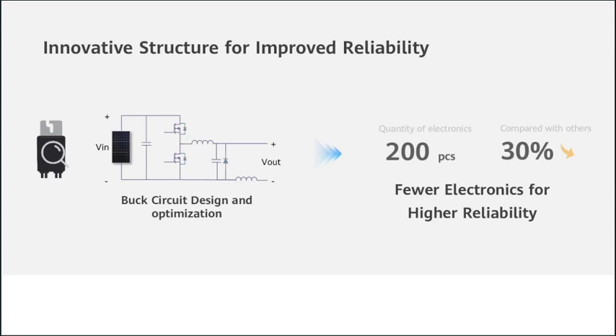Important, of course, is the reliability of the components you are putting on your roof, not only the PV modules, but of course also the optimizers. That's why we have a very innovative buck circuit design for our optimizer, very slim and reduced in the electronic part count. We have only around 200 electronic components typically inside of each optimizer, and this is a very robust design. As our optimizer works with our inverter, and the inverter has the MPP tracking fully integrated, we do not need a full MPP tracking on each module integrated in each optimizer. That's why we can work with less electronics for higher reliability on the rooftop.